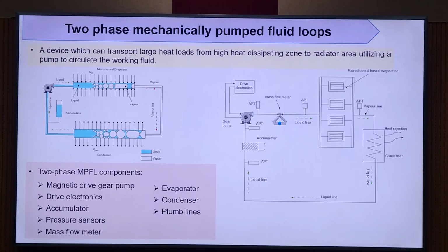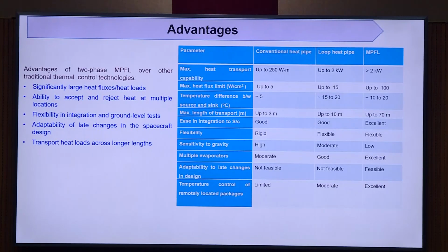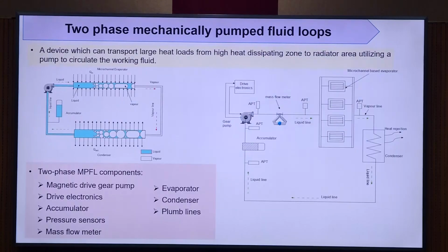So coming to two-phase mechanical pumped fluid loops, this is a device which we have recently developed, and it is in an advanced stage of development. Two-phase MPFL is a device which can transport large heat loads or heat fluxes from the evaporator to the condenser using a centrifugal pump or a gear pump, with a working fluid, where boiling happens at the evaporator zone. This is the evaporator where the heat dissipation happens, and because of the heat load, the fluid converts to vapor and travels to the condenser zone, releasing the heat of evaporation.